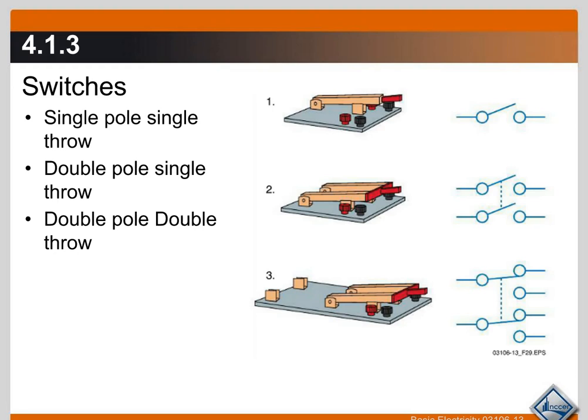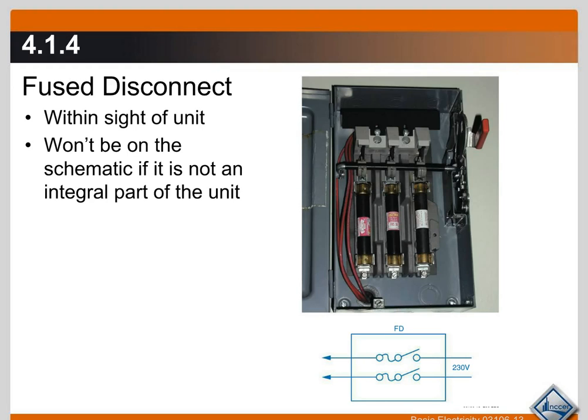Fused disconnect. This is usually outside of the unit and it is installed as part of the installation. It doesn't come with the unit themselves. Just for safety reasons, the fused disconnect or any type of service disconnect needs to be within sight of the equipment. Can't be in another room or out of sight where if you turn it off, someone can accidentally turn it on because they don't see you or you don't see them.